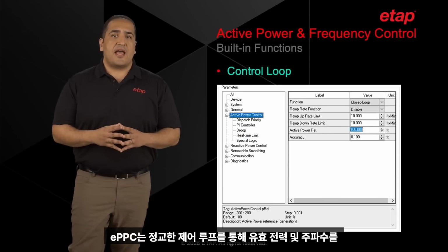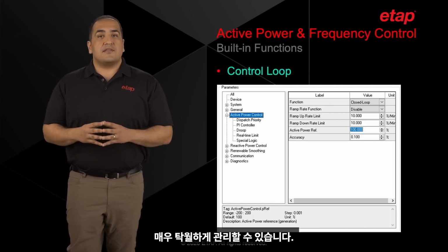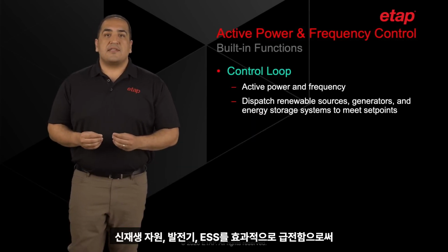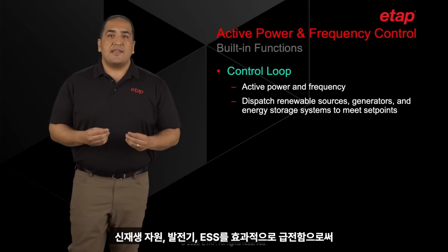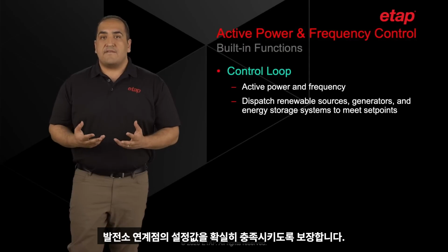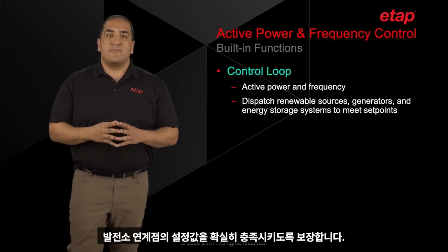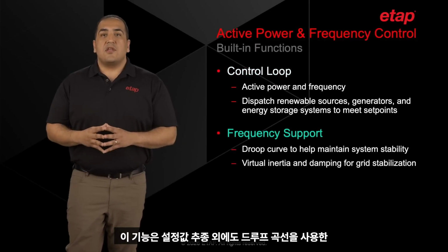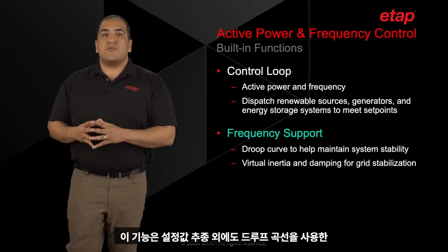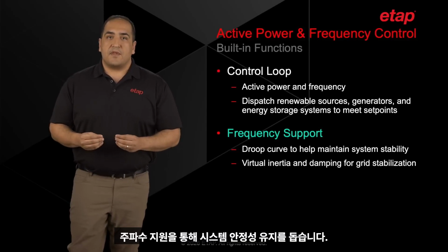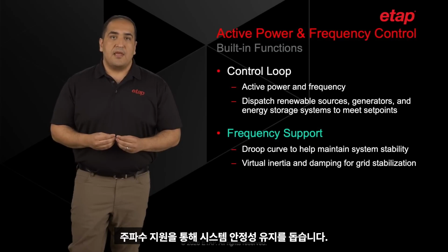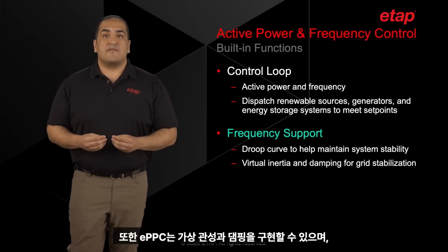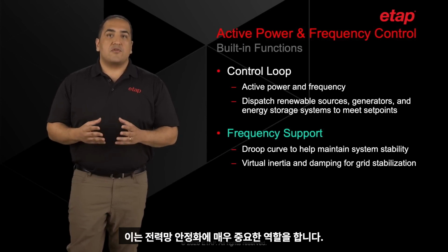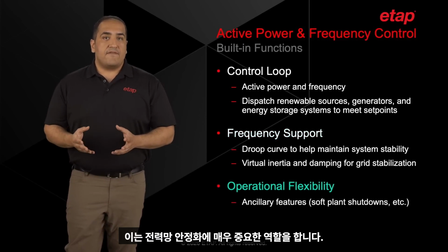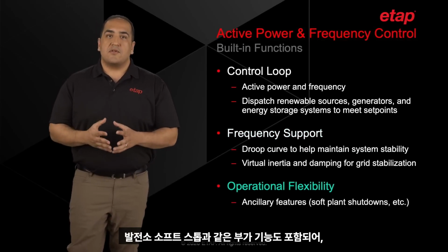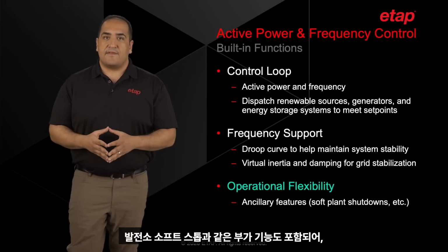ePPC excels in managing active power and frequency through a sophisticated control loop. It ensures that renewable resources, generators, and energy storage systems are dispatched effectively to meet the set point at the plant's point of interconnection. This function not only tracks the set point, but also provides frequency support using a droop curve, which helps maintain system stability. Additionally, ePPC can implement virtual inertia and damping, which are crucial for stabilizing the grid. Ancillary features such as soft plant shutdowns are also included to enhance operational flexibility and safety.